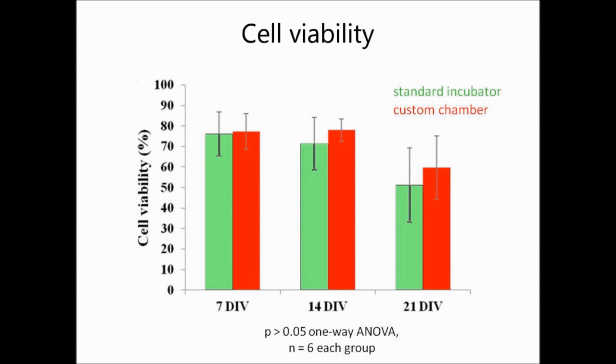Glass coverslips were incubated for 21 days and the neural viability was measured with dead/live staining. Cell viability was comparable to standard incubators.